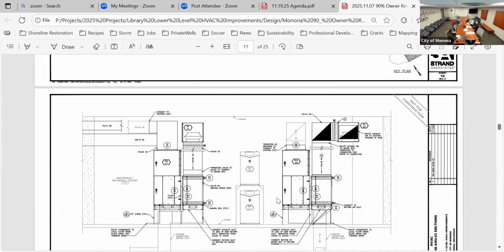And most of the piping for the water can stay in place, and that's all pumped off the boiler plant. So really, we'll just be able to leave most of the copper in the ceiling, replace the pump that pumps the water, and then replace the heating coil with a VAV unit. So that's a portion of the project.